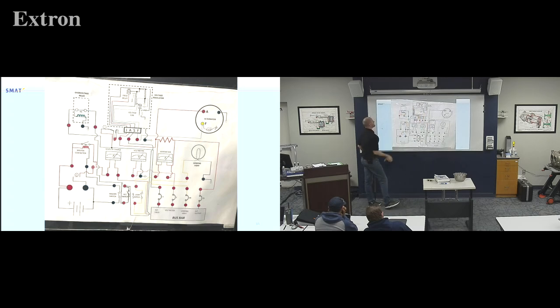If our over voltage relay were to get too high of voltage, it's going to open that, and the only way to reset it is to reduce the power coming into the inlet side of it, which means, if you follow the wire all the way back, you pop the alternator field circuit breaker, that turns the power off, and it resets. Then we kick it back on, and as long as it's not over voltage, it'll allow it through again.